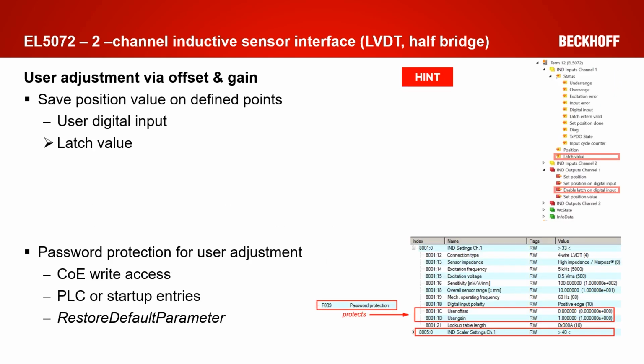Once more, some hints from my side. To automate and simplify the user adjustment, you can use the digital input. This offers you the possibility to store the measurement value at a fixed time. In our wording, it's so-called latching the value. So for example, you can travel to your mechanical zero, latch the measurement value by using the digital input, then it will be written in a separate register. You can read out this register and just write this automatically to the CoE data. You can do the same with the gain adjustment.